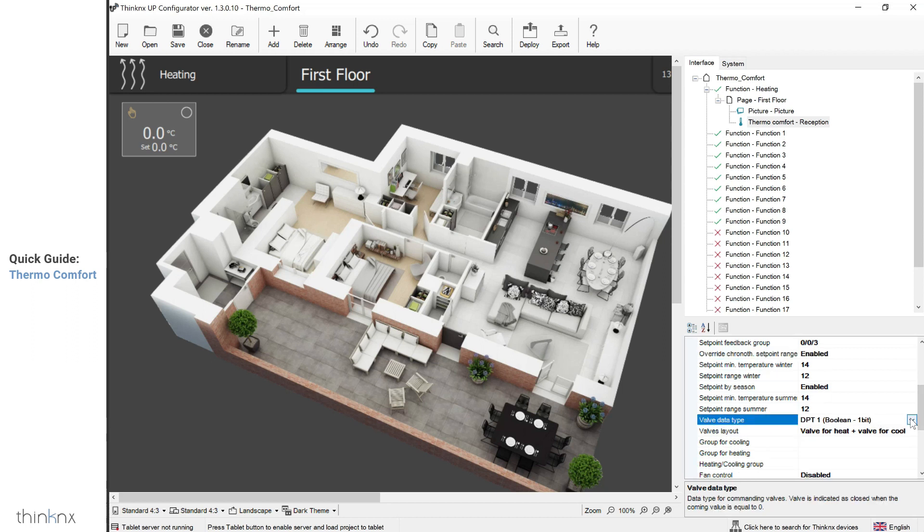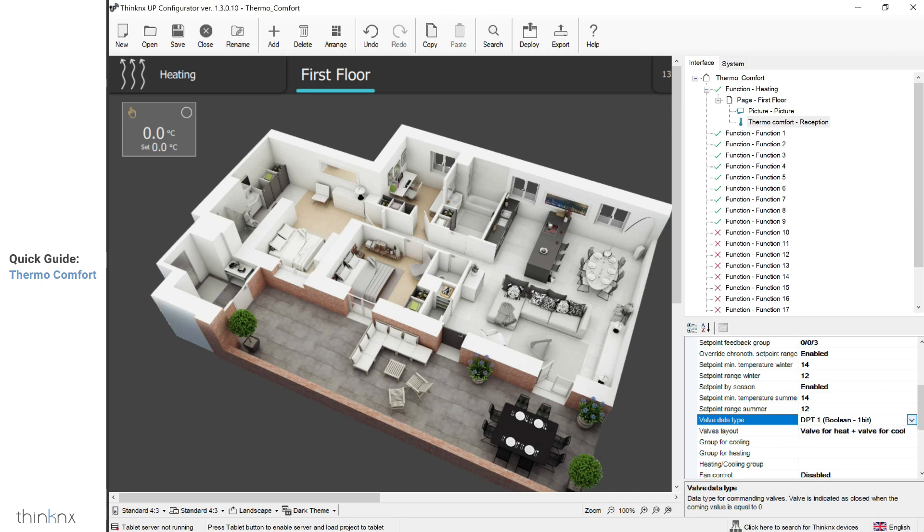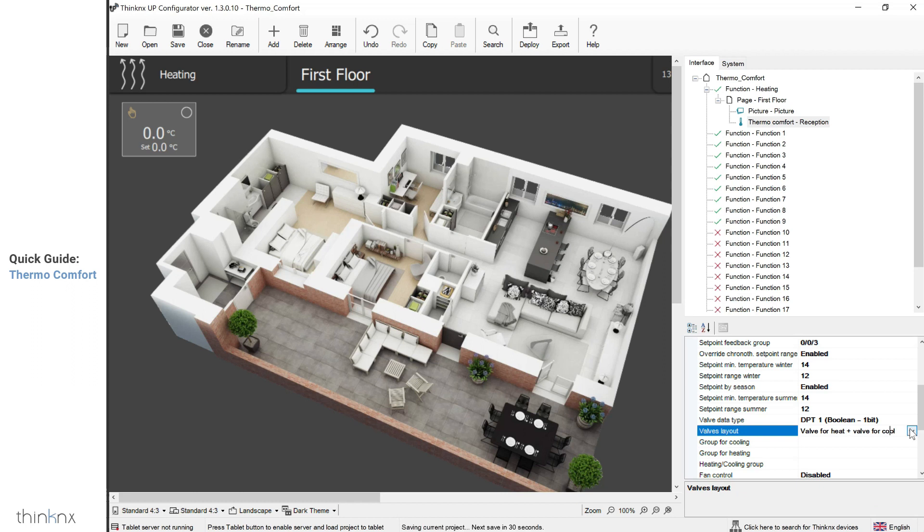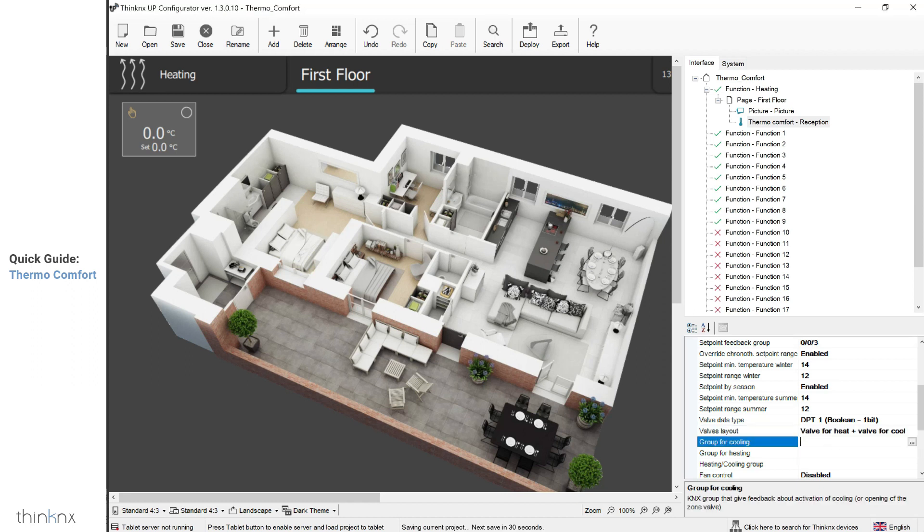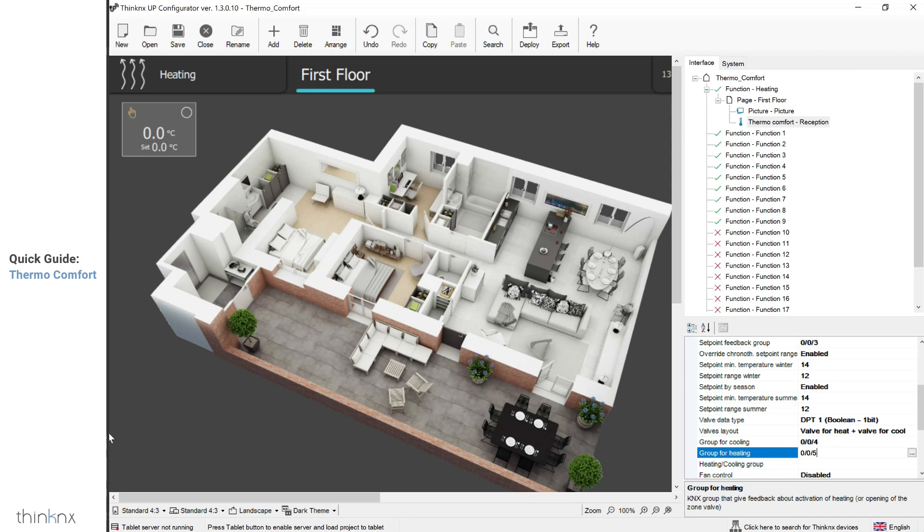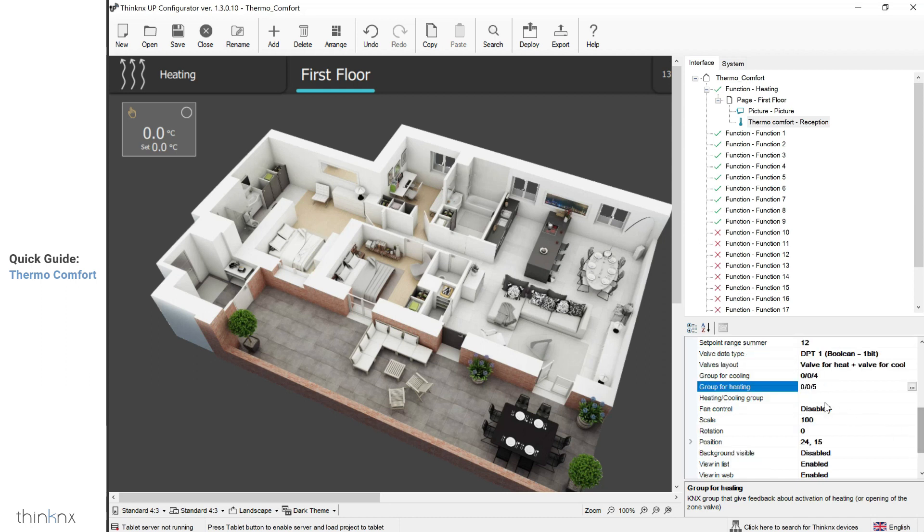Next, it's time to configure the valve. First, select the valve type. Then, choose whether the valve is used for both heating and cooling, or you have a different valve for each mode. Enter the related group addresses for the valve. Note that these groups are only meant to be read as a feedback by the server. They are not used to control the valve.